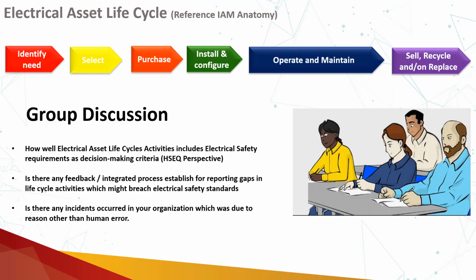design a system with less than 12 cals or 20 cals per centimeter square of incident energy, then being an HSEQ person, you can talk to them about why you should propose an arc resistant switchgear. So what is an arc resistant switchgear?